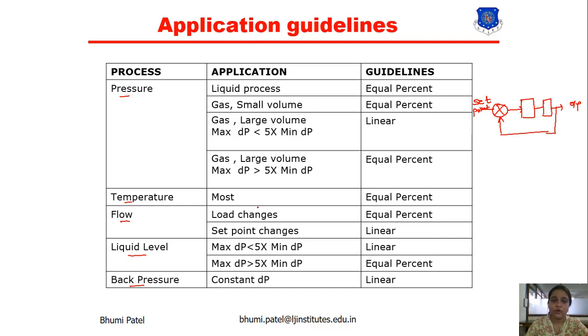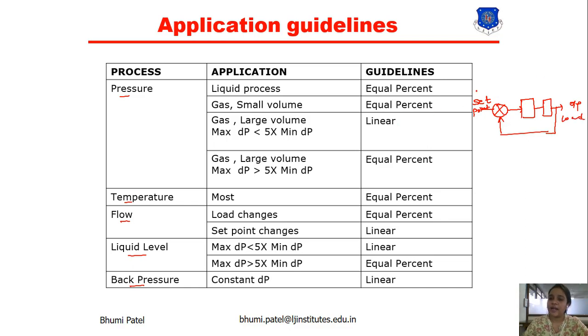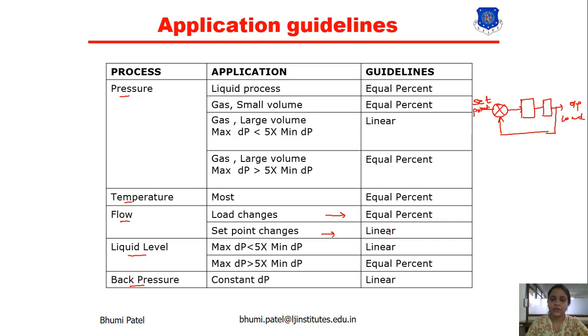The second application is load changes. The load is the final output of the system. If we continuously change the set point and still cannot get the desired output, we change the load of the flow system. For load changes, we use equal percentage characteristics, and for set point changes, we use linear characteristics.